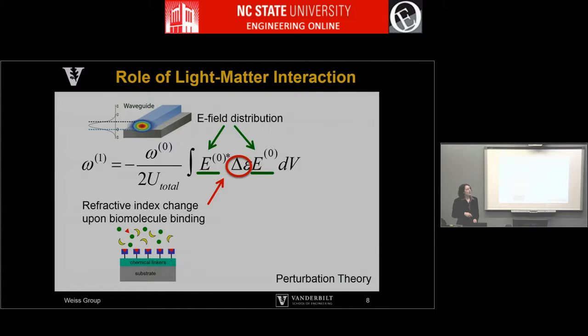So this comes about when you add molecules to your surface. Initially, you would have an ambient that's air, or a buffer solution or a liquid. And then when you bring your molecules to the sensor surface, you've changed the dielectric environment. And here, again, is the importance of rinsing away, because if we leave these other contaminant molecules in the vicinity of the sensor, they can also increase this delta epsilon. And that isn't due to the presence of the molecule you want to detect. It's due to these other contaminants. So you need to rinse these away before taking your measurement.